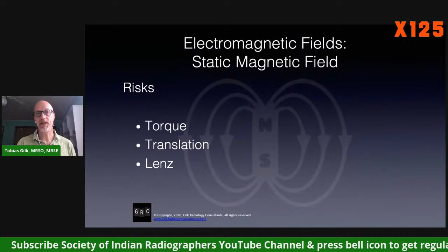So let's break these three risk factors from the static magnetic field down a little bit further. Torque. What are the contributing effects that make torque-related risks greater or lesser? Well, torque is a function of a number of different factors. And let's start with the ferromagnetic properties of the object. And here I'm going to be speaking about the contributing factors of objects or devices that we bring into the MRI area. We can't modify the static magnetic field of our MRI scanner. It is what it is. So I'm going to talk with you about identifying the nature, the characteristics of materials that we might be bringing towards the MRI and how they contribute to the risk.